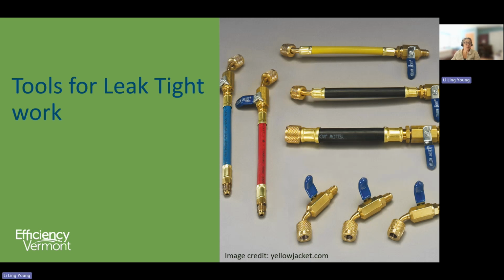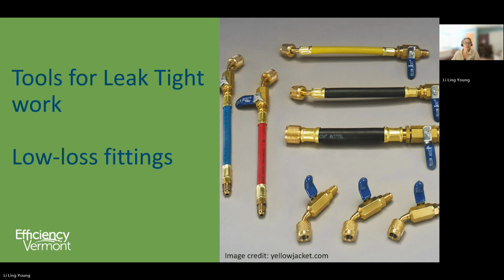There are tools that will help make leak-tight systems and that will minimize the loss of refrigerant during service. Low-loss fittings keep refrigerant in the hose when the hose is disconnected from the service port, and that's especially important on the liquid line. Stranded refrigerant can be reintroduced into the system on the suction side, but make sure the hoses were purged of air before filling with refrigerant so you don't introduce non-condensables back into the system.